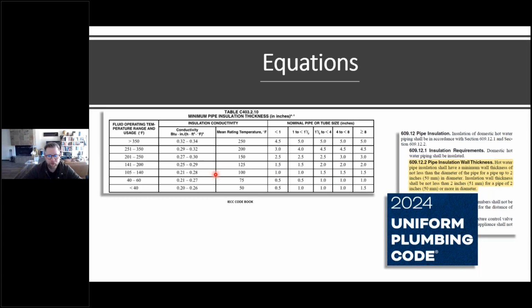Now, the question comes up, if you set your water heater at 140, should I use the 105 to 140 row, or should I use the 141 through 200 row? Take a look at your water heater manufacturer specific product information that gets installed, because most water heaters have a plus or minus 2%. So you could end up overshooting the 140 set temperature, in which case a code official may ding you and require you to go with the thicker insulation, or turn your water temperature down so you don't exceed that. So it has happened. It's one of those things to be thoughtful of. The Uniform Plumbing Code has a different provision in there, which is to match the insulation wall thickness to the pipe diameter, which does have a more uniform BTU per hour per lineal foot loss. And we'll touch on that in a little bit, but those are the two methods out there currently.